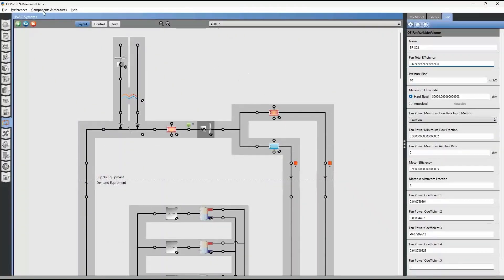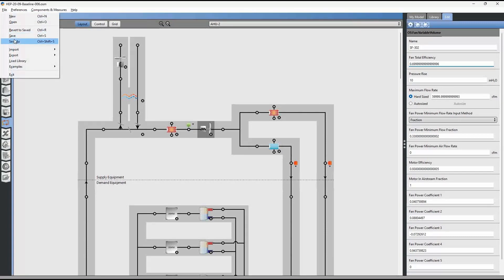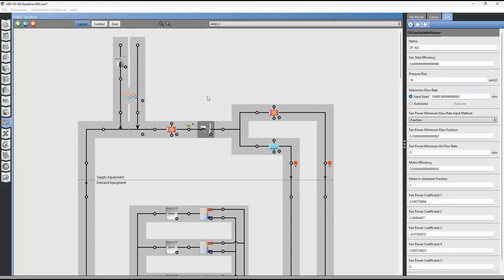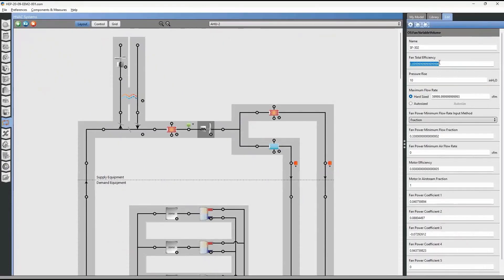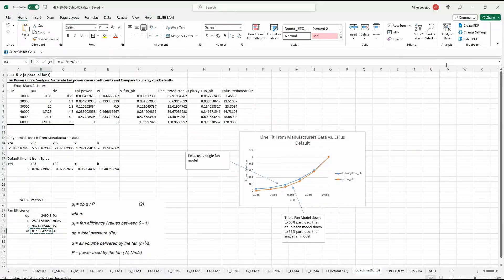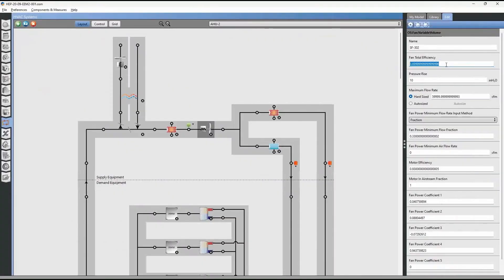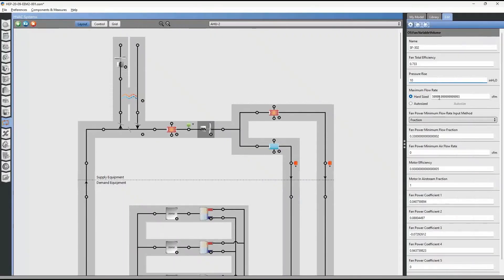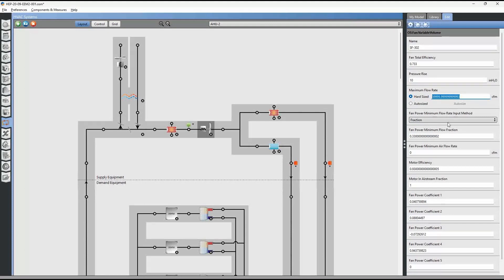So we are going to save this as a different version. So we can compare the models later. And we will edit the fan total efficiency to this value here. So that's the new fan total efficiency. Our pressure rise is going to remain the same. And we have a 10 inches of water column here. And same with the airflow. That is also going to remain the same.